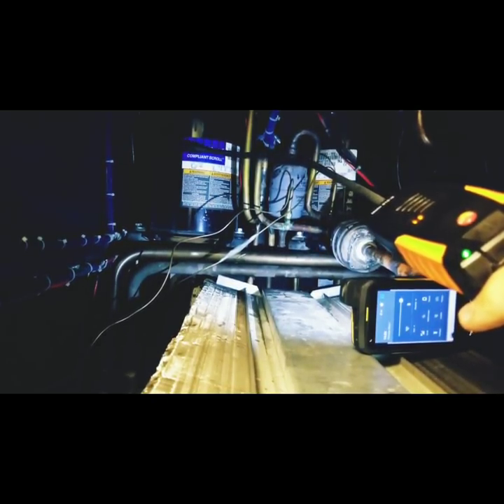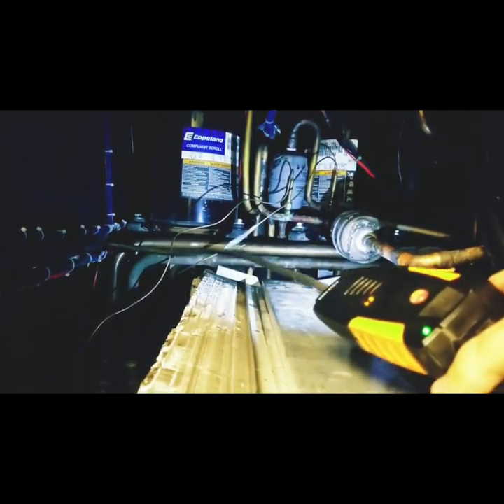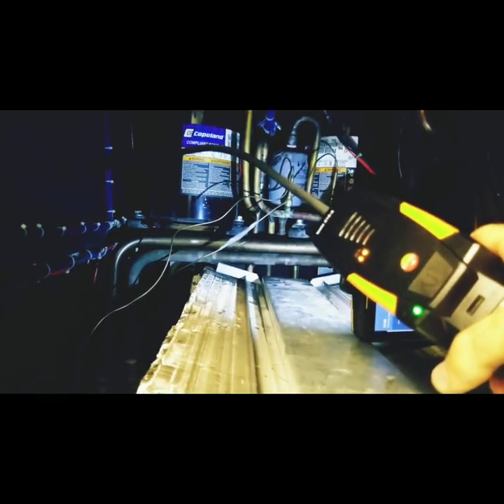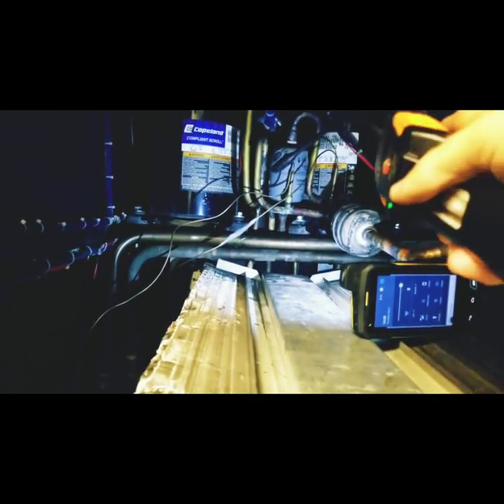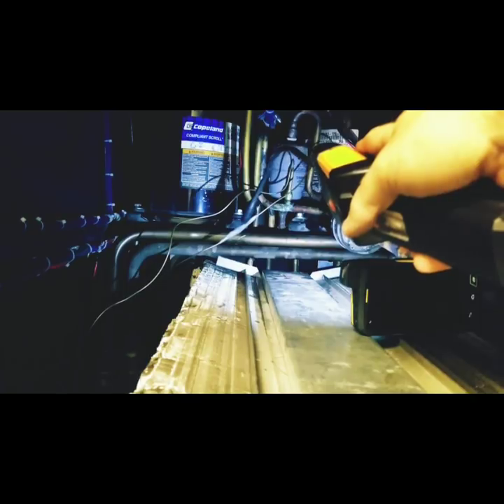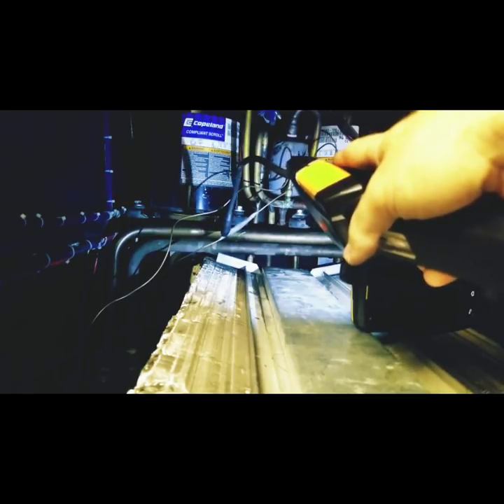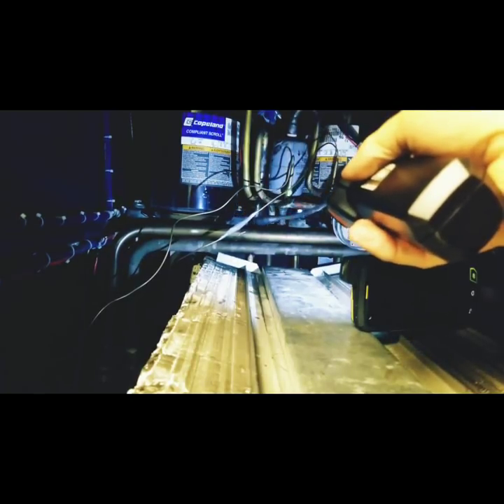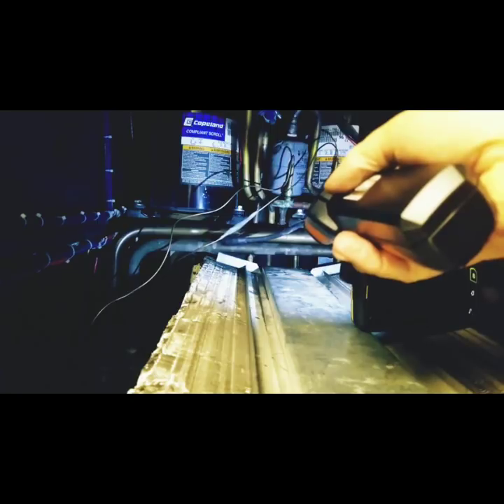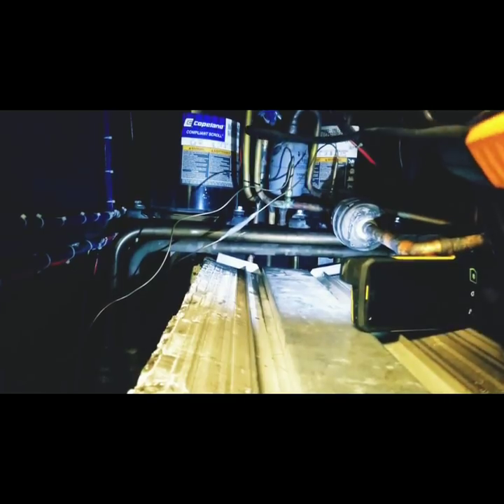One last test. The leak detector is completely reliable at finding leaks, so if it tells me there's no leak here I'm going to trust it. We're going to hit the Smart Seal External with the leak detector. Looks like we're good — leak repaired, evacuation, charge complete. Good to go. Happy HVACing.